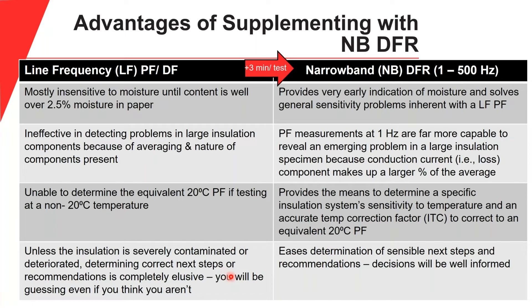Narrowband DFR testing is very sensitive to moisture and solves a lot of the general sensitivity problems inherent with line frequency power factor testing. Because we go down in frequency to one hertz in a narrowband DFR test, this allows far better ability to see an emerging problem in a large insulation specimen — at these very low frequencies, conduction current makes up a larger component of the total charging current, so any resistive losses become more visible. Narrowband DFR also helps with temperature correction, which we'll discuss when we talk about ITC. As a screening test, narrowband DFR helps guide next steps when problems are indicated — with line frequency power factor alone, deciding what the next step should be can be elusive, and narrowband DFR eases that determination.